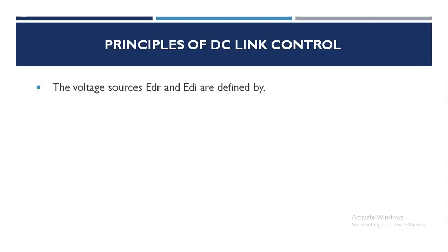The control of power in a DC link can be achieved through the control of current or voltage. From minimization of loss considerations, it is important to maintain constant voltage in the link and adjust the current to meet the required power. This strategy is also helpful for voltage regulation in the system from the consideration of the optimal utilization of insulation.